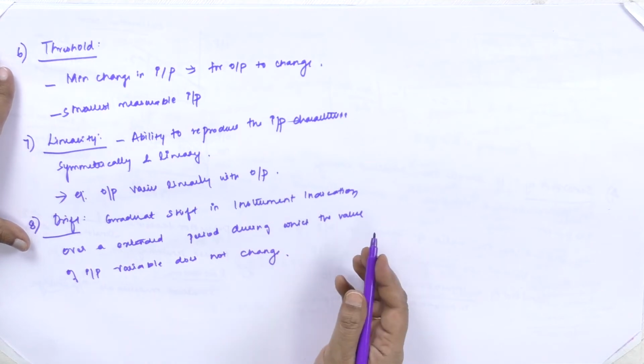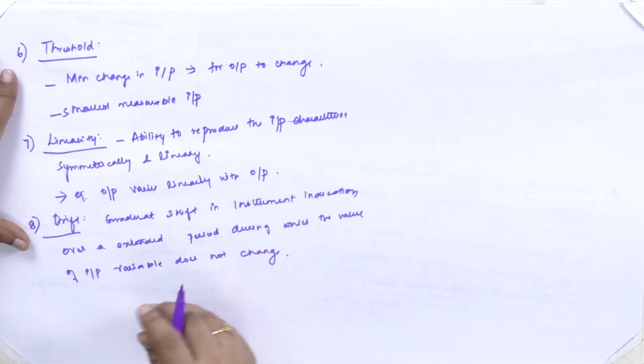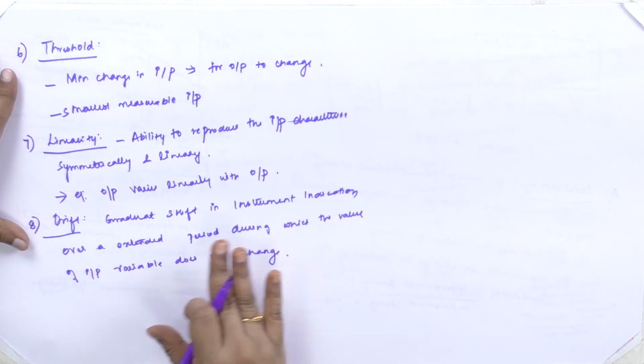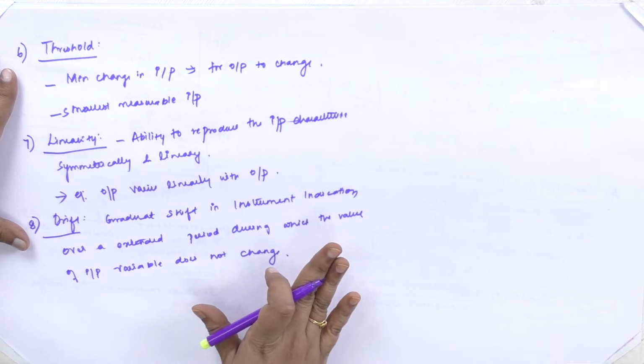So, it is a gradual shift in the instrument indication or reading over an extended period during which the value of the input variable does not change.